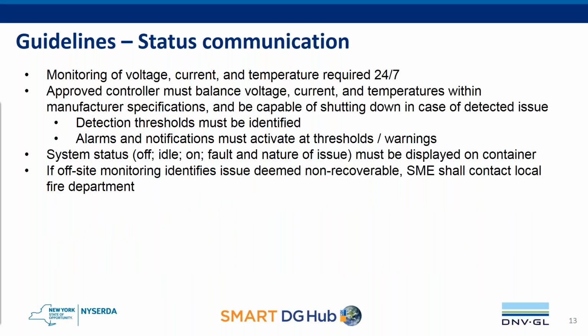For status communications, the key features that need to be monitored are voltage, current, and temperature. That monitoring is required 24/7. It is required that there be an approved controller to balance those values. And again, Department of Buildings and FDNY is not in the business of dictating what the safe ranges of operation are for your system, but you need to know what those safe ranges are, and you need to provide them up front.